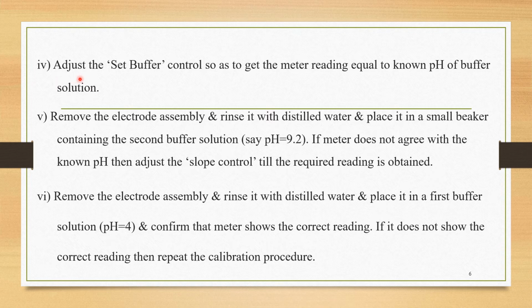Now first of all, we take the buffer solution of pH equal to 4. Whenever we insert the electrode assembly into that pH 4 solution, we have to adjust the buffer control to a value which gives the meter reading equal to the pH of the buffer solution, and that is 4. So unless and until it gives pH equal to 4, we have to adjust this buffer control.